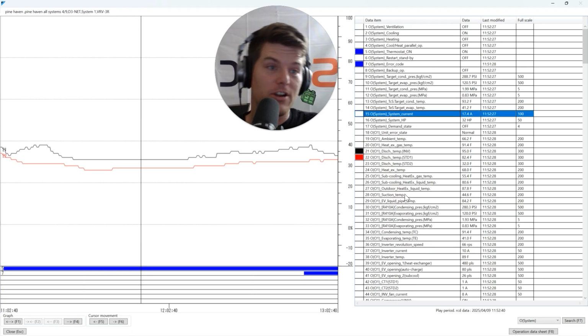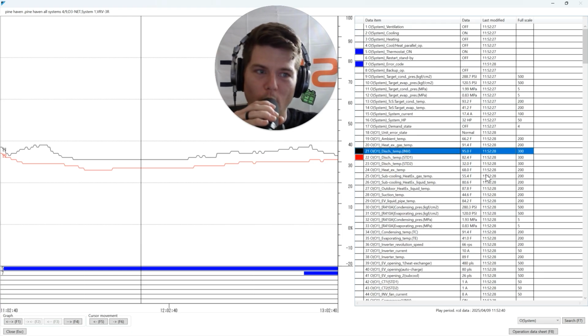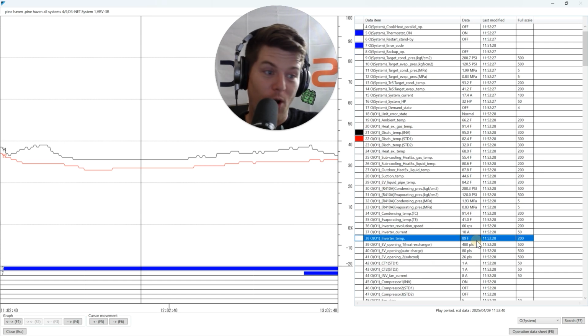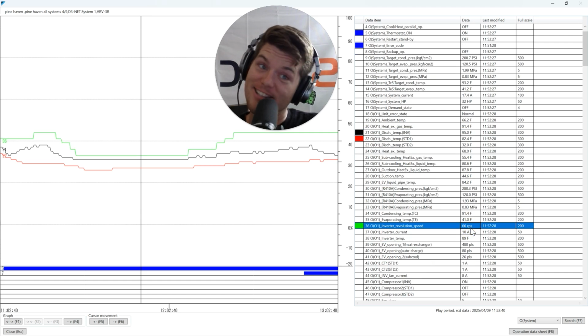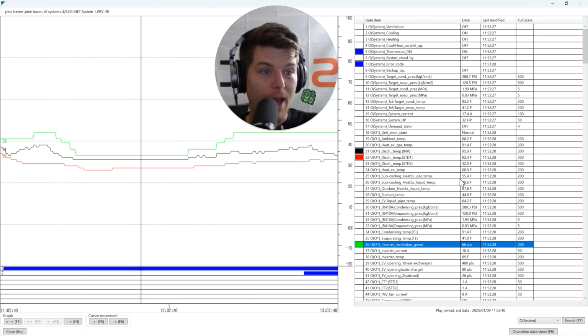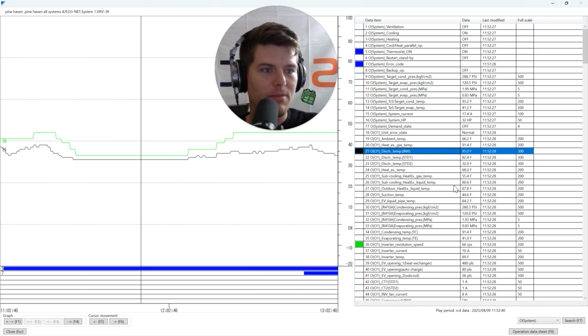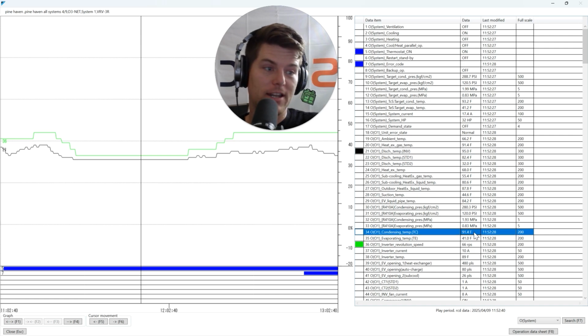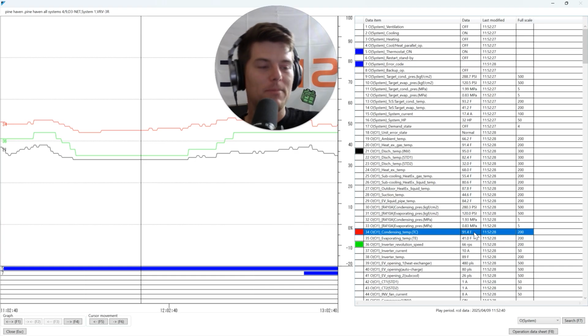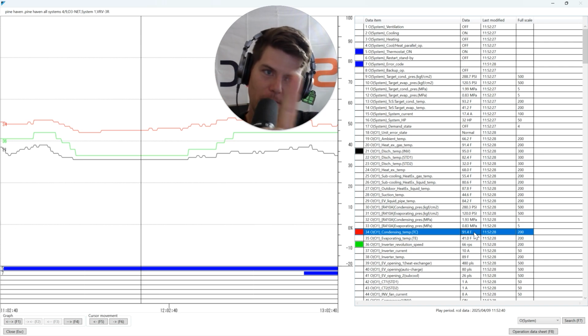All right, so you're going to sit here and you're going to say, whoa. Discharge inverter temp, 95 degrees. It's not running. Oh, but she's running. Look at that, 66 RPS. And she's just chugging away here, and she's happy to be here. She doesn't know why she's here, but she's here. 95 degrees. What's my condensing temp? Holy crap, 91.4 degrees. That's barely a 4-degree discharge superheat. That is low. So what do we know about low discharge superheat? It only means one thing, everybody.